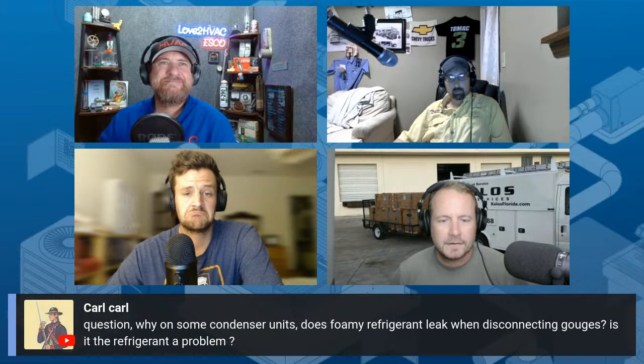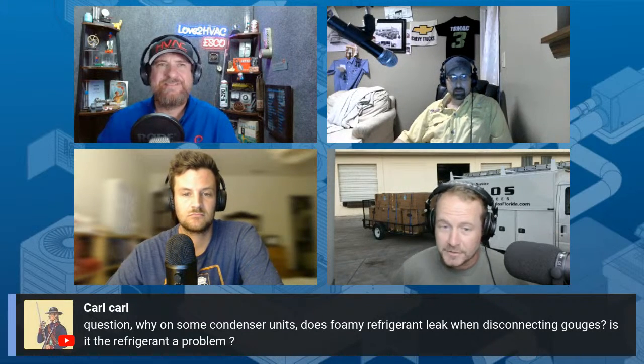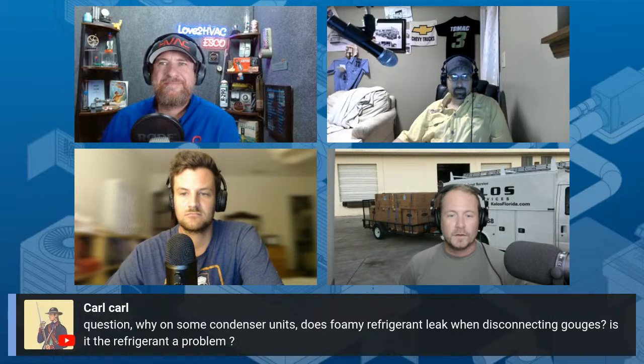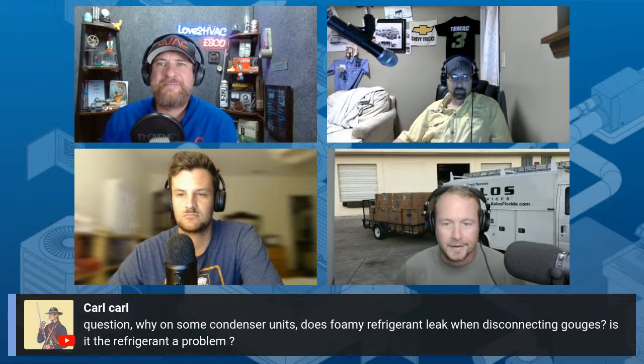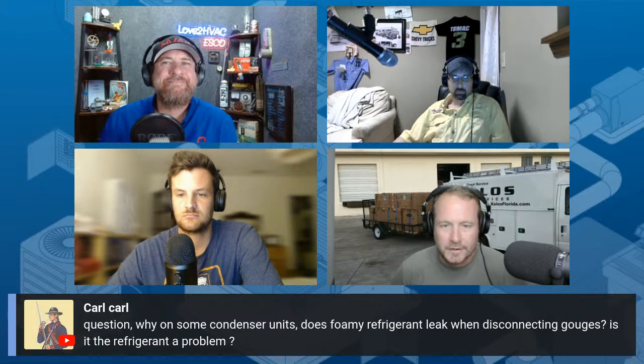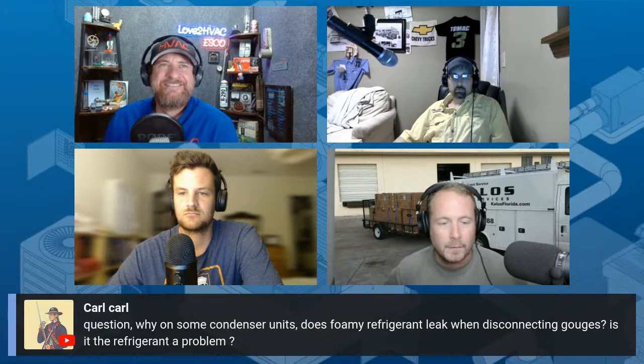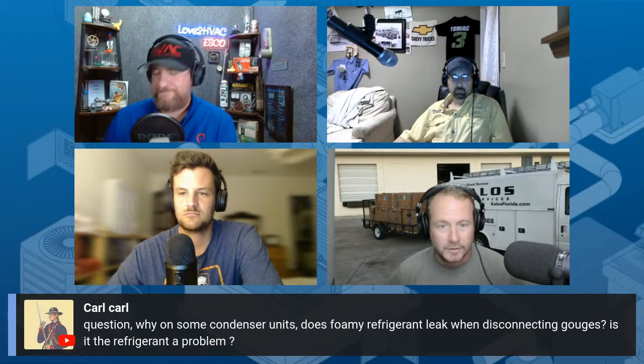I'll also add, additives can be a factor. If you have cases with really low airflow, you get poor oil return. There are different factors that can drive it—maybe somebody put a lot of additives in, or swapped a compressor for another compressor and now there's too much oil in it. What you're seeing is oil, almost certainly.